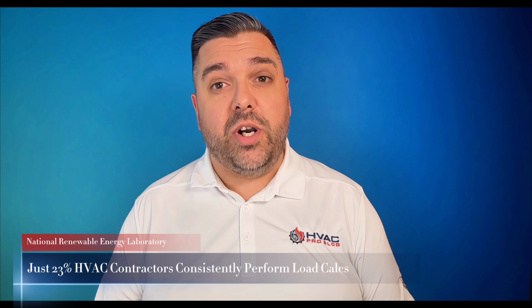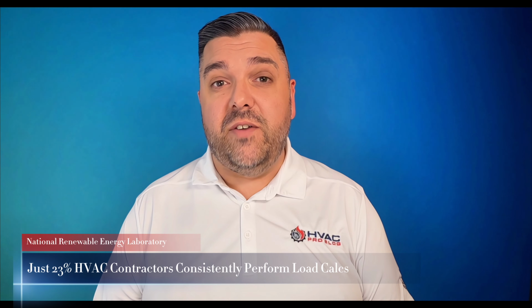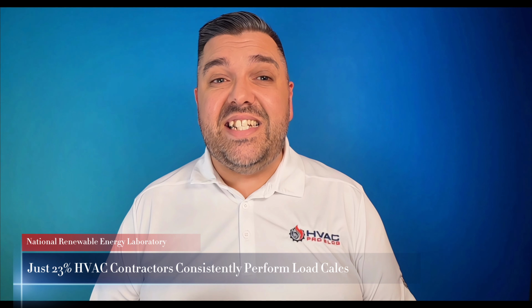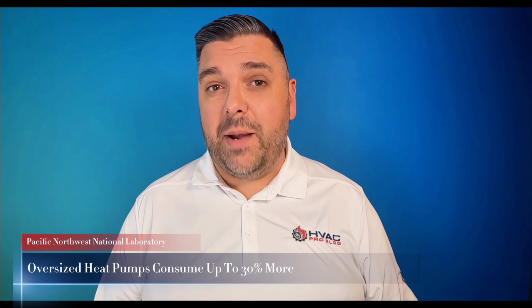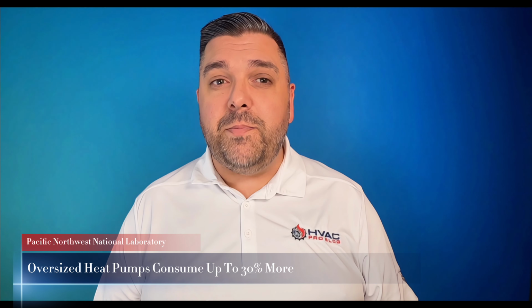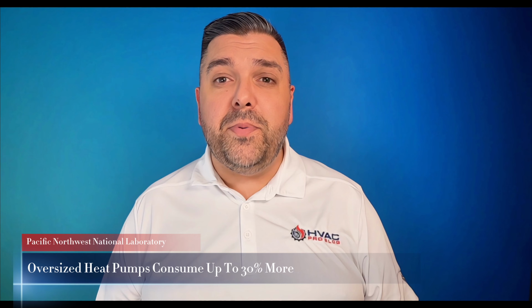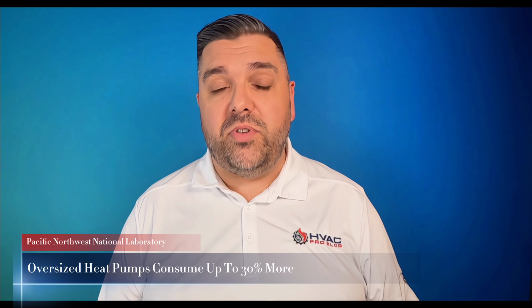According to research from the National Renewable Energy Laboratory, only about 23% of HVAC contractors consistently perform Manual J load calcs. That means 77% are sizing equipment based on what? Square footage rules of thumb? The old equipment nameplate? Or whatever fits the budget? Here's why this matters more than most contractors realized. A 2018 study from the Pacific Northwest National Laboratory found that oversized heat pump systems can consume up to 30% more energy than properly sized units.